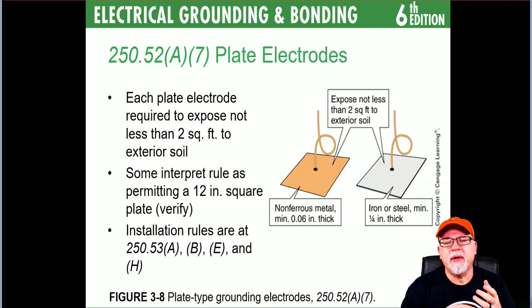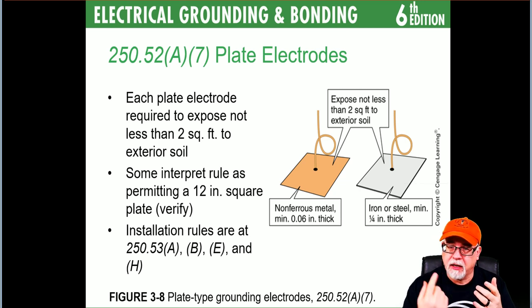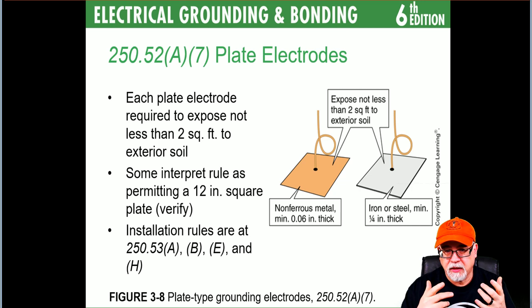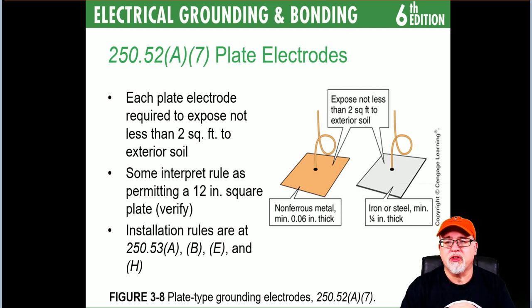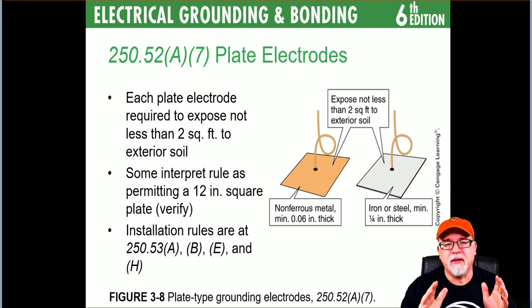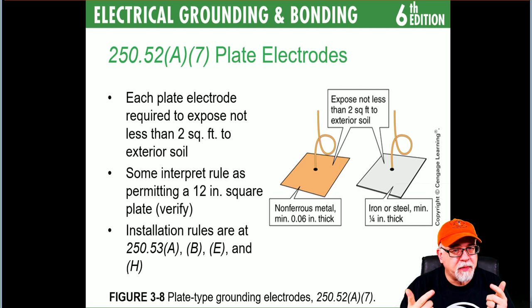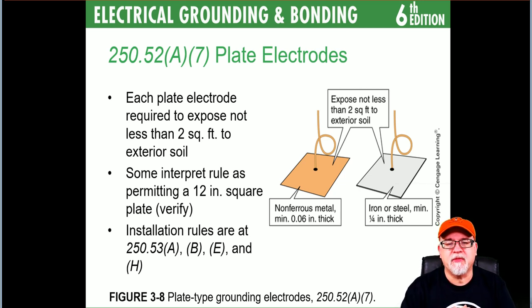250.52(A)(7) — plate electrodes: each plate electrode is required to expose not less than two feet to the exterior soil. Some interpret this as permitting a 12-inch square plate — check with your local jurisdiction. Literally speaking, it can't be less than two feet square in contact with the soil. When you buy these plates, manufacturers already understand the rules. Installation rules are in 250.53(A), (B), (E), and (H).